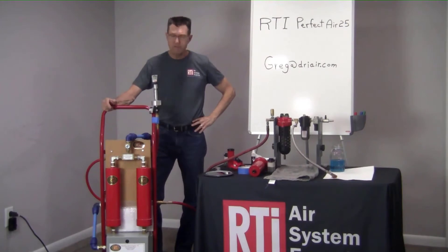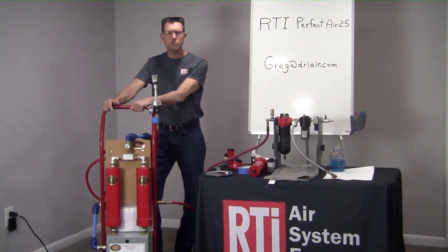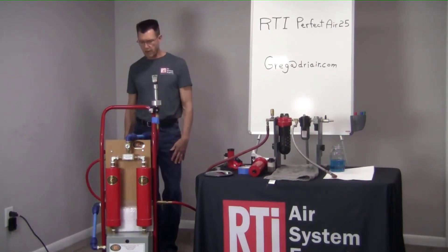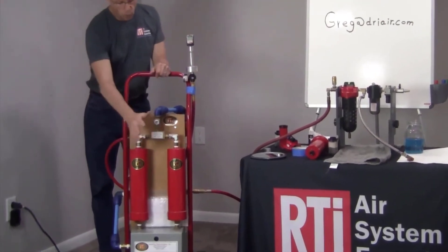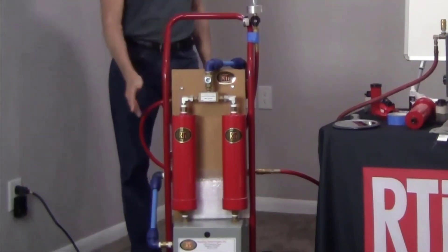Perfect Air 25 is a regenerative desiccant system used for painting in body shops and in other types of finishing applications where we want to lower the moisture content down below 1% compressed air humidity. Right now I've got about 50 psi coming into this system and it's purging itself out and regenerating the desiccant on one side. One side will be used for drying the air while the other side gets a portion of the dried air through it to regenerate it.